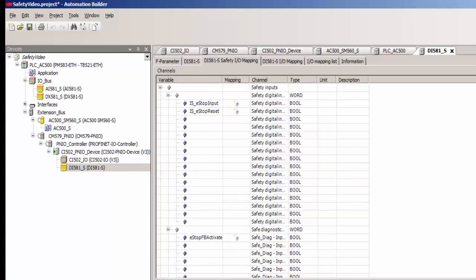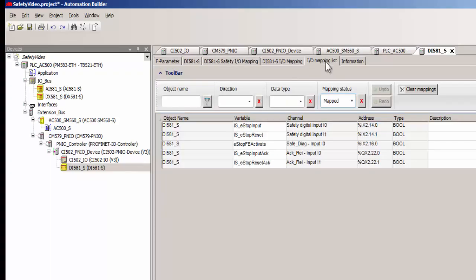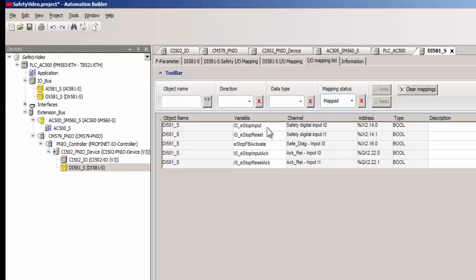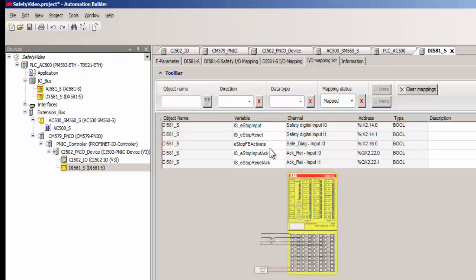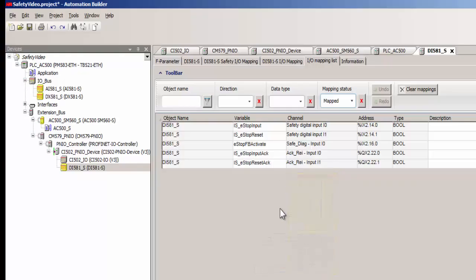To make the example simpler, the I-O mappings are already created as seen in the screen. The signal name is created for channel 0, which is default combined with channel 8. The two contacts of the emergency push button are wired to channel 0 and channel 8 in this particular case. Since this is a two-channel configuration, the signal may need to be mapped only for the lower channel, here it is channel 0.